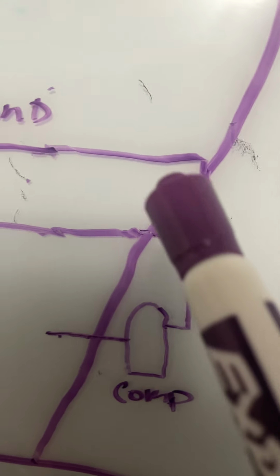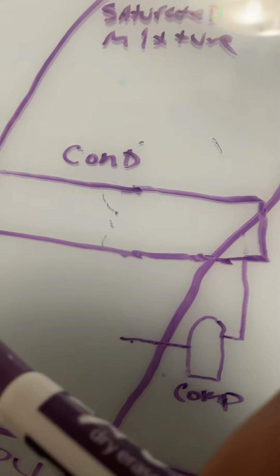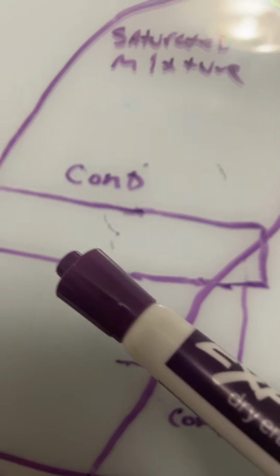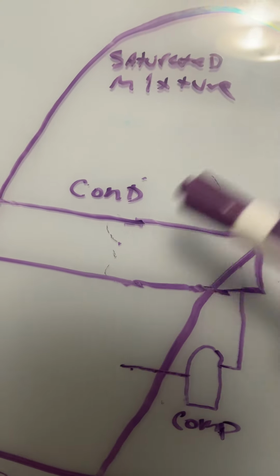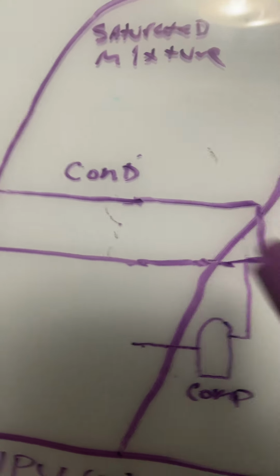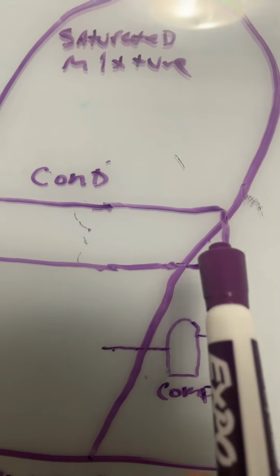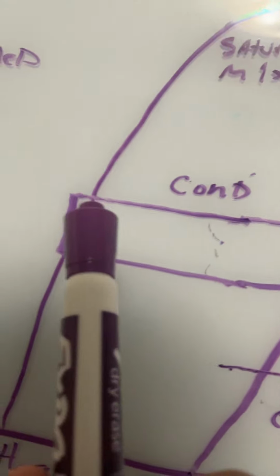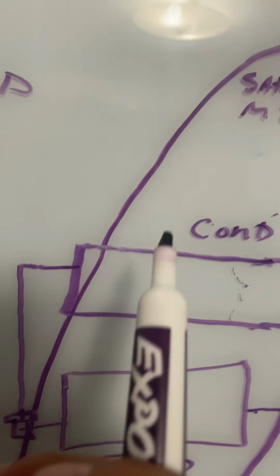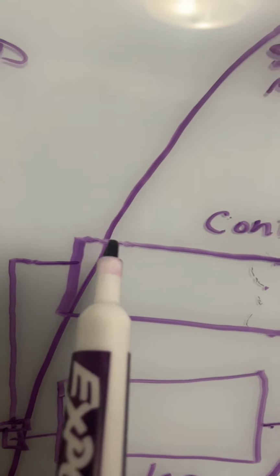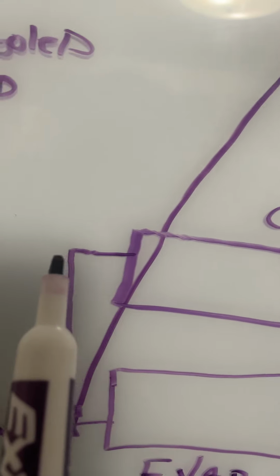It enters the condenser coil, which has air passing across it. As the air passes across that refrigerant, it rejects the heat into the atmosphere. As the heat is being rejected, that superheated vapor is going to de-superheat, and then it will become a liquid at the outlet. Now that we became a full liquid, this here is the liquid line.